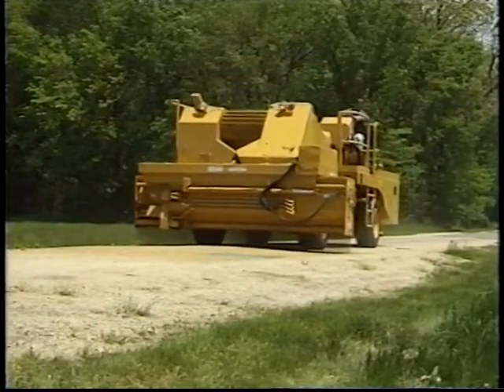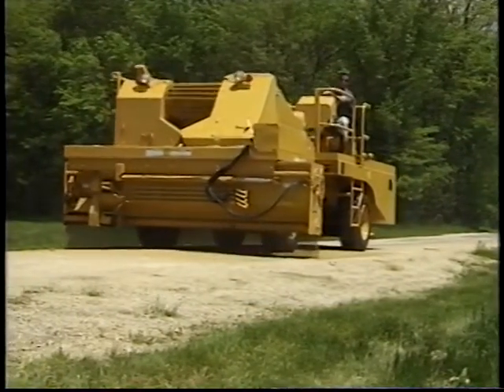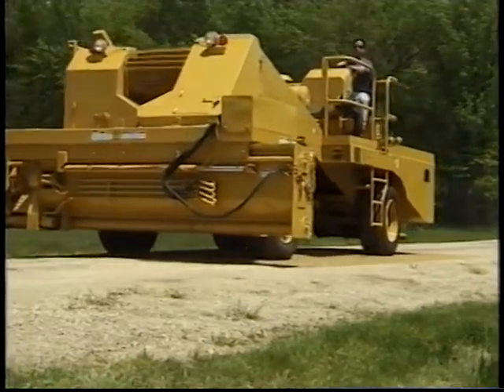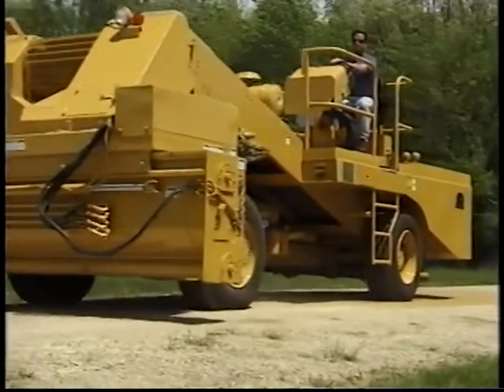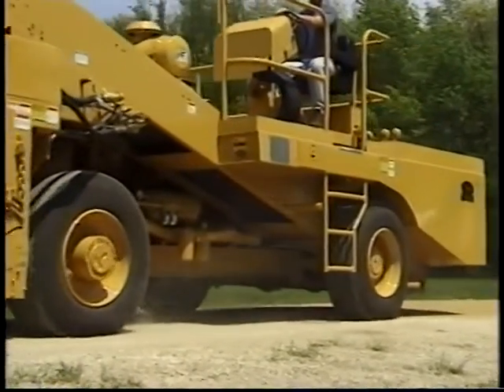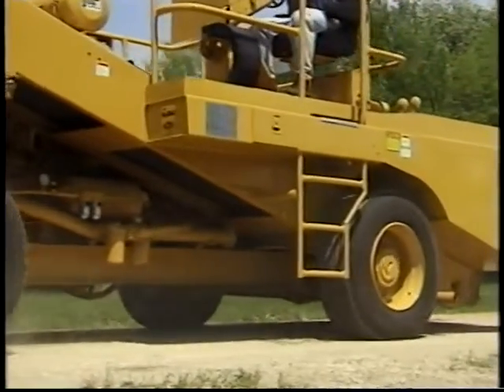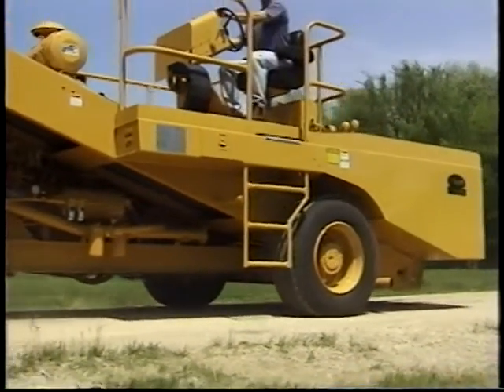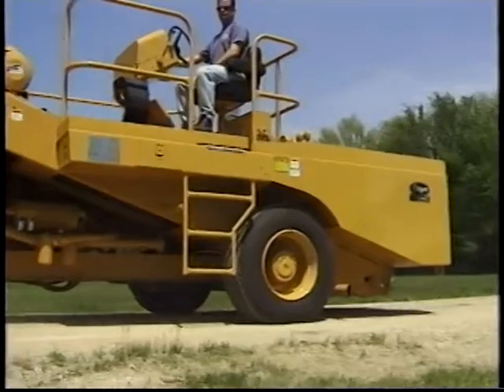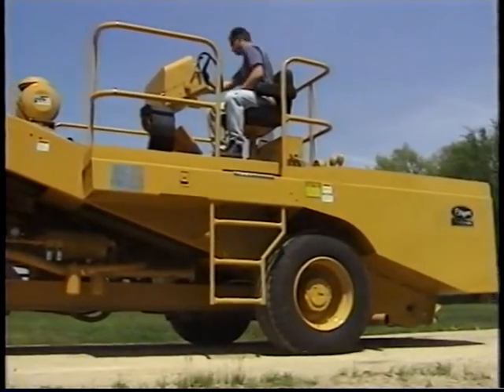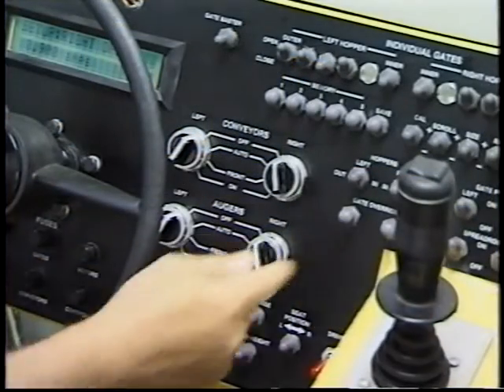The calibration done in these setup screens is to adjust the open and close thresholds on the proportional valves controlling the gate cylinders. These thresholds determine the speeds at which the gates open and close and allow the operator to adjust them independently from side to side to make them open and close at the same speed.